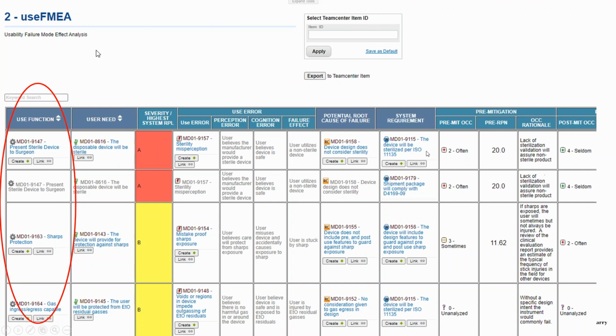So one example of system requirements then would be to say the way we're going to establish that sterility is through compliance with 11135. Now, that system requirement carries with it all of the design requirements, the IQ, OQ, PQ, and the validation requirements associated with EO sterilization. But we can't define that particular system requirement without first understanding that the device needs to be sterile, how that device is going to be presented to a physician, and what is the sterilization method. So you can imagine that system requirement has a lot baked into it, right?